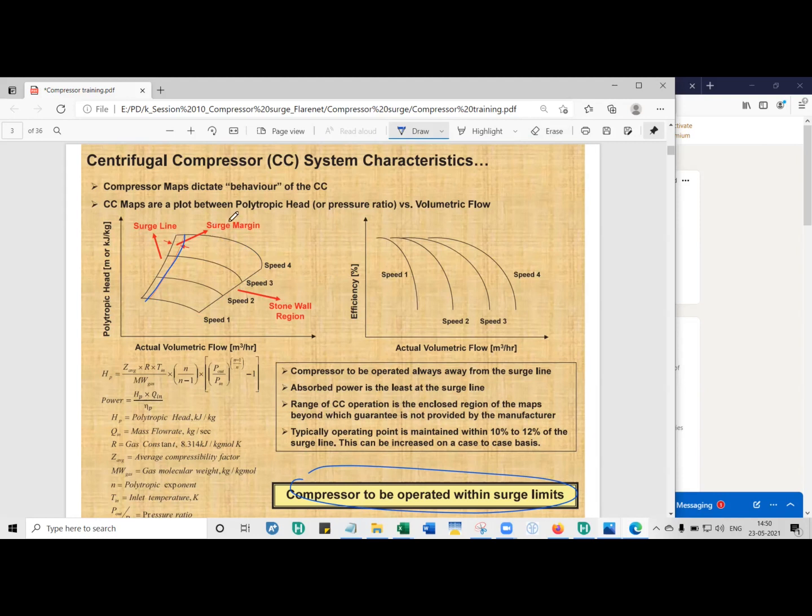So the surge, so I haven't shown here, but in reality, it's called SCL, surge control line. Surge control line is the point where the anti-surge system will kick in and do whatever it takes to pull the compressor out of the surge region. And then on the other end, you have what is called SLL, surge limit line. No matter what happens, you're never meant to cross the surge limit line.